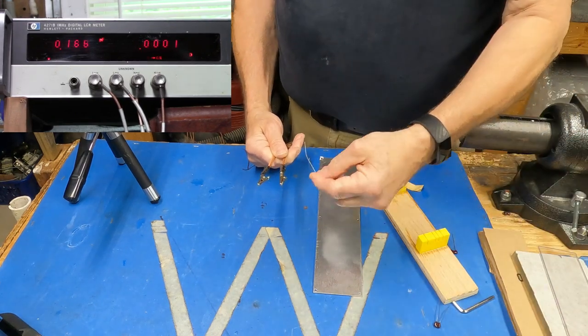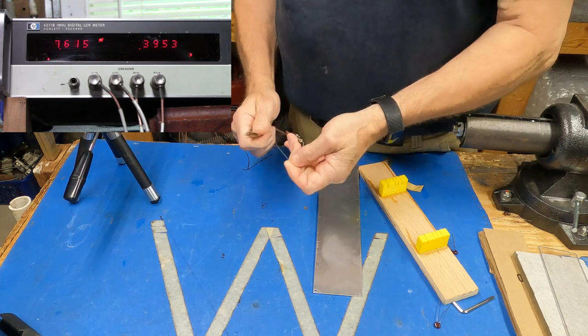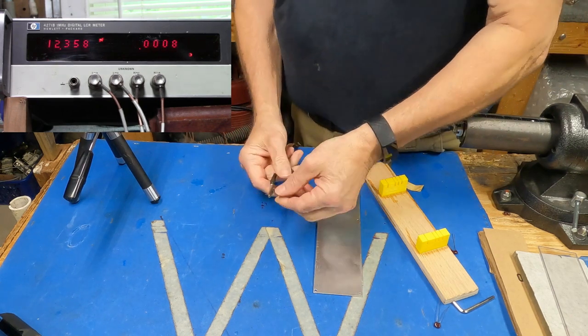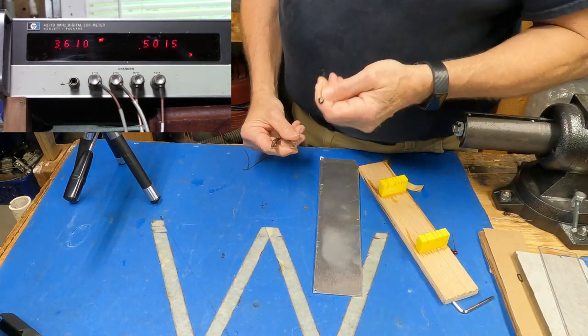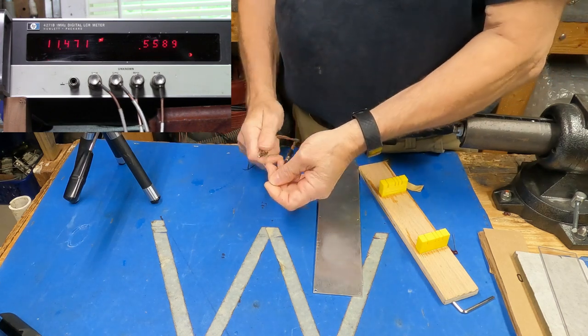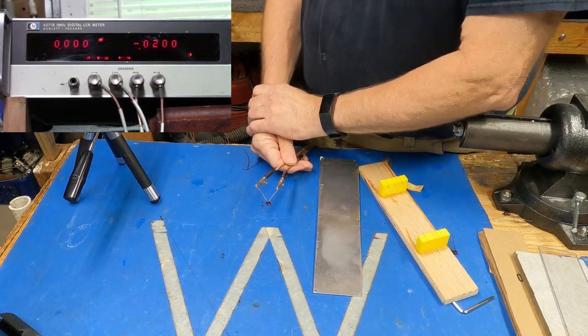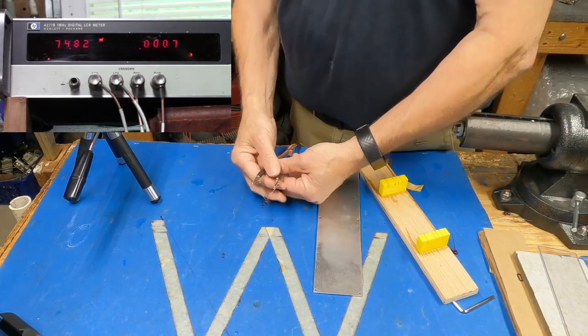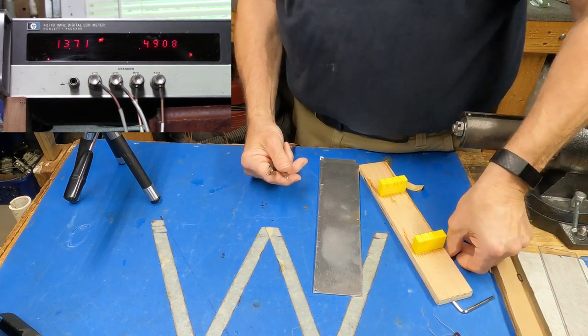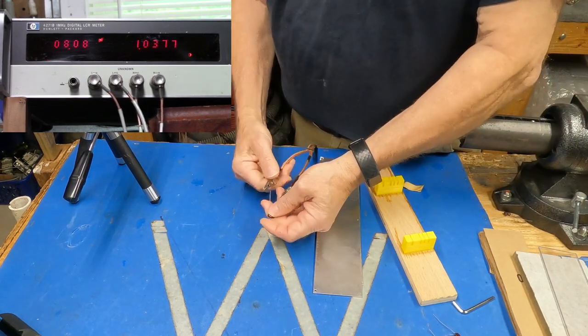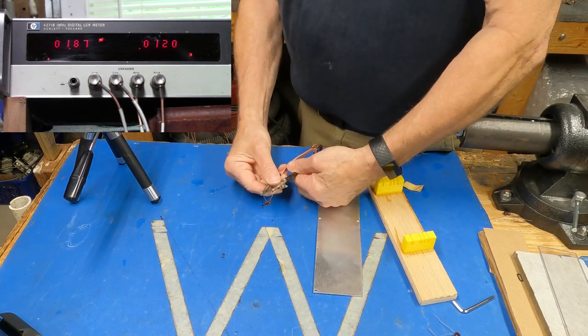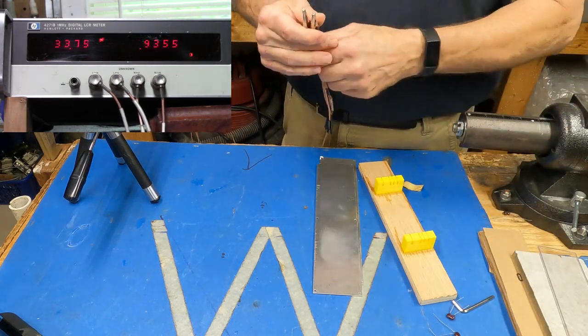So, here I have three capacitors. We'll take a real quick look at them. This one, I believe, is 12 picofarads. Okay, 1%, 12.5 picofarads. This one is probably the 68 or the 75. Yeah, this is the 75. So, 75.86, that's dead nuts on, right, within one percent. And this one, I believe, is 120 picofarads. 119.56. So, the instrument's in good shape, and so are those capacitors.